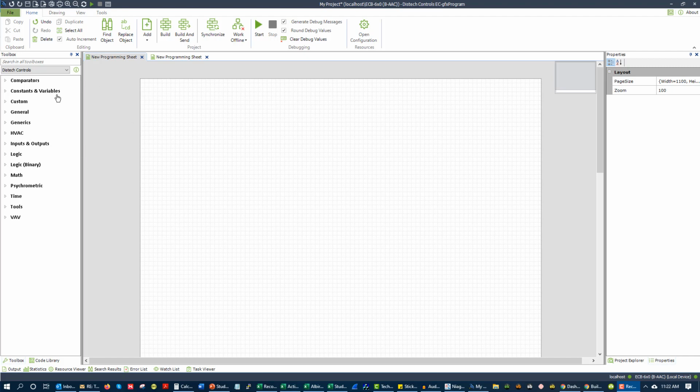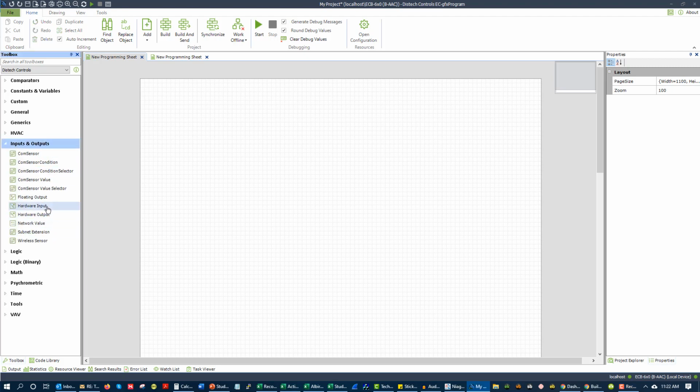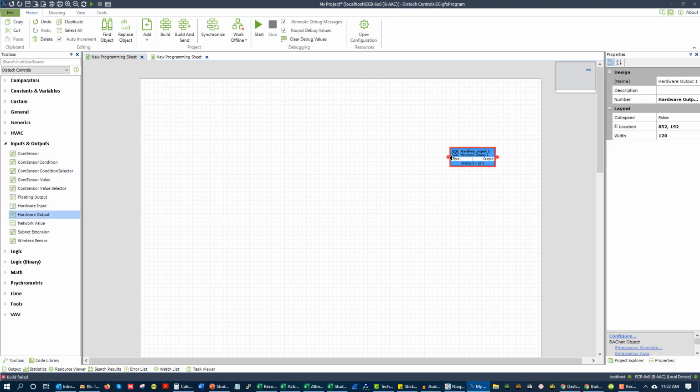The first control mode we are going to talk about is a pretty straightforward control mode, which is just digital output, Boolean output, binary output. Doesn't really matter, but basically what it is, you are taking an output and you're turning it on or off. The output only has two states. It can either be on or it can be off. We see this in turning on unit heaters. We see this in turning on fans. We see this in driving isolation valves open with an on-off command. So this is a very common controls mode that we're going to be going through.